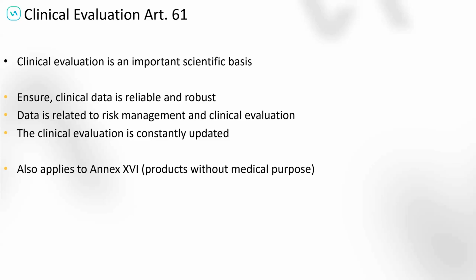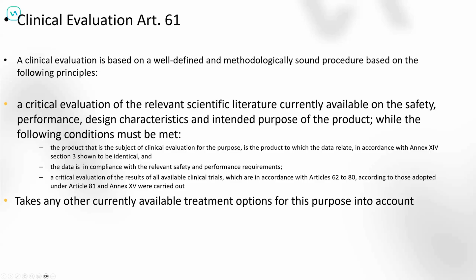I have a few things you need to take into account which are really important. What I said: you can use clinical literature if the product is safe and has the same design characteristics, either because the product has particular setups which make it equivalent, or you need to have it in a certain other way through literature analysis for devices which are currently in a clinical trial in the same case as you, with an intended purpose comparison. All that needs to be done in the clinical evaluation plan, and sets up the right setup and the right path forward. On one side you get the input from the safety and clinical side, from the GSPR, the general safety and performance requirements, which you need to fulfill, and then the literature gives impact on the risk management, post-market surveillance, vigilance if needed, the clinical review which you conduct for your device, the CAPA and the change control procedure.